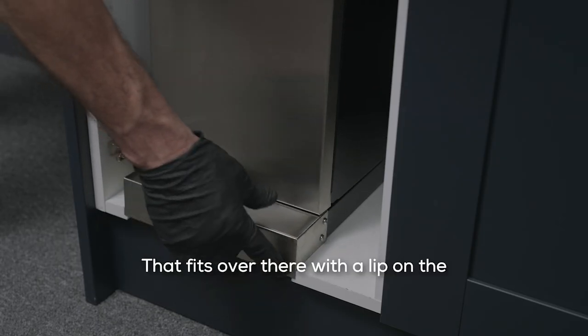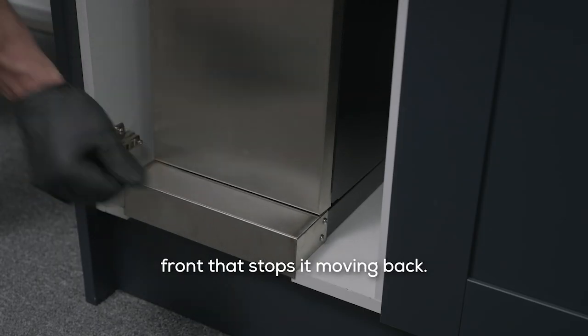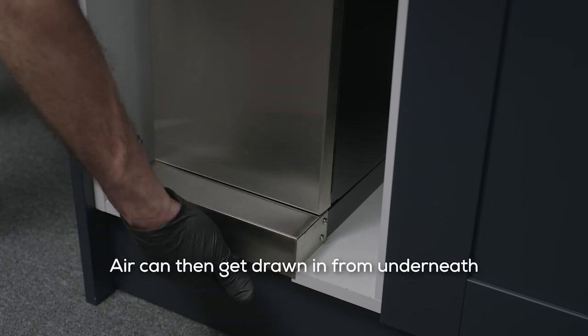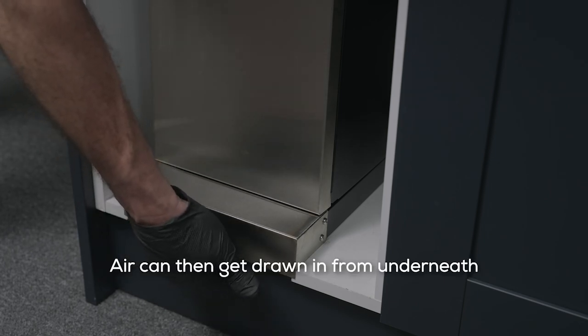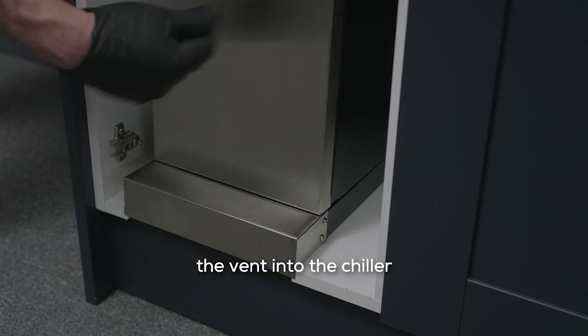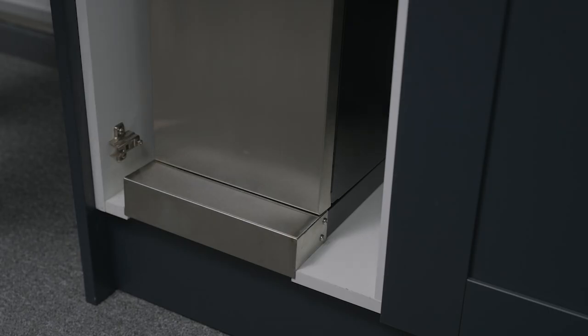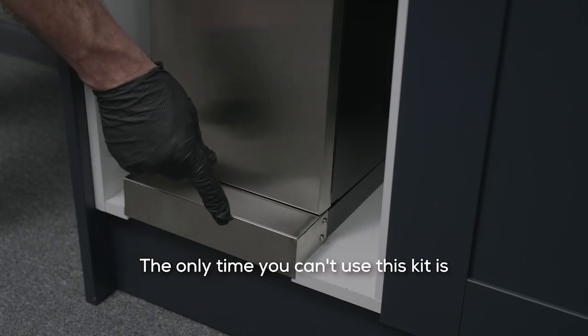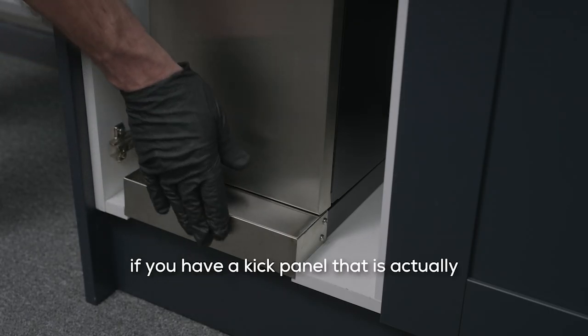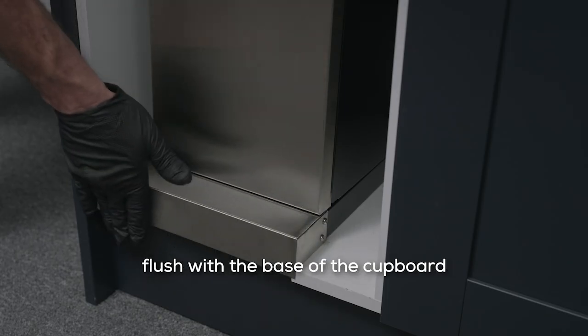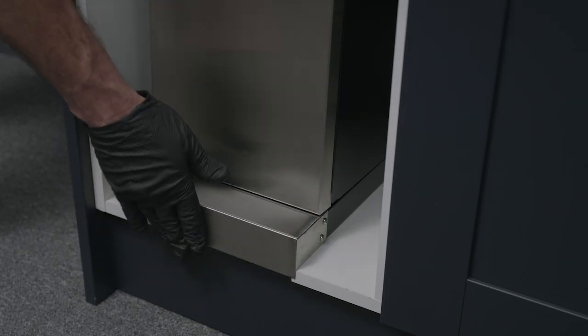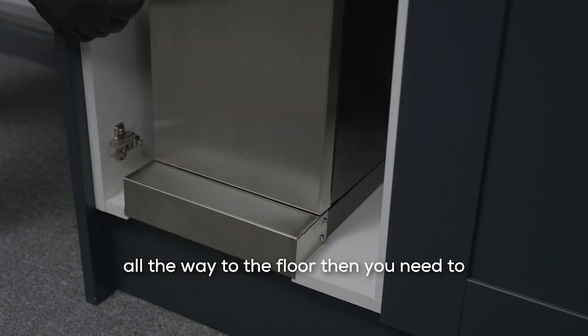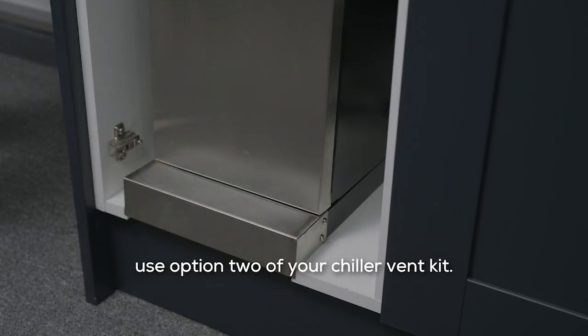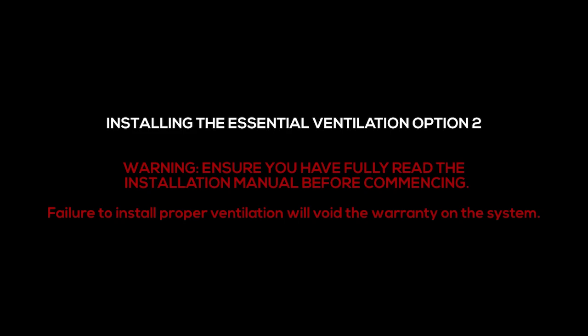That fits over there with a lip on the front that stops it moving back. Air can then get drawn in from underneath the vent into the chiller and exhausts out the back. The only time you can't use this kit is if you have a kick panel that is actually flush with the base of the cupboard, or if you have a cupboard door that goes all the way to the floor, then you need to use option two of your chiller vent kit.